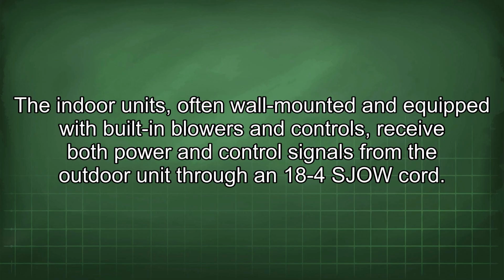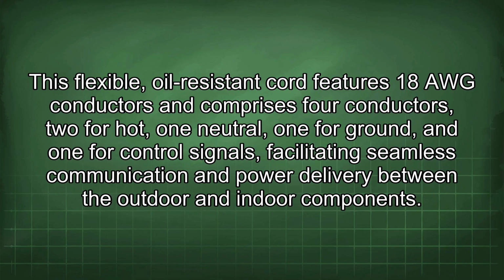The indoor units, often wall-mounted and equipped with built-in blowers and controls, receive both power and control signals from the outdoor unit through an 18-4 SJOW cord. This flexible, oil-resistant cord features 18 AWG conductors and comprises 4 conductors, 2 for hot, 1 neutral, 1 for ground, and 1 for control signals, facilitating seamless communication and power delivery between the outdoor and indoor components.